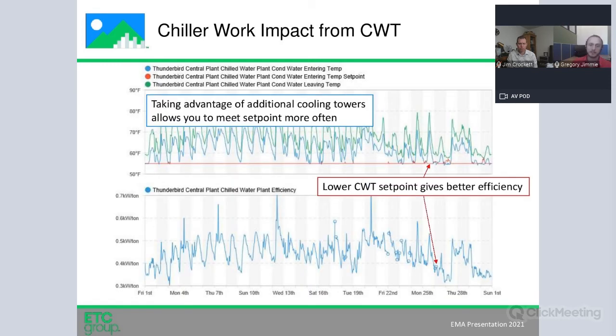Next slide here kind of gives a visual example of that. So you can see here that we've actually dropped this system down to about a 58 degree condensing temperature. And this, I want to say, is in November in a Phoenix area, same hospital. But you can see that we're hitting that red line, not very often.